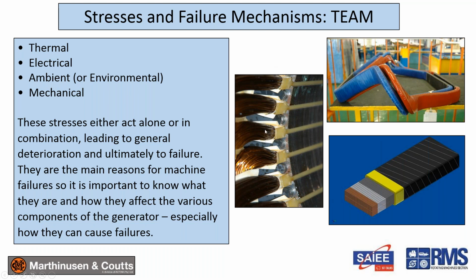Again, I mentioned the presentation is mainly about high voltage main insulation, but I just wanted to keep the low voltage in there, and specifically rotors as well, because the whole point of the presentation is that the primary aspect of insulation to consider is not just your dielectric stress, your kilovolts per millimeter.